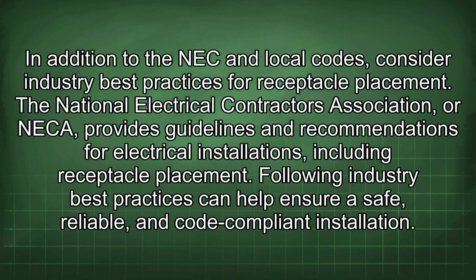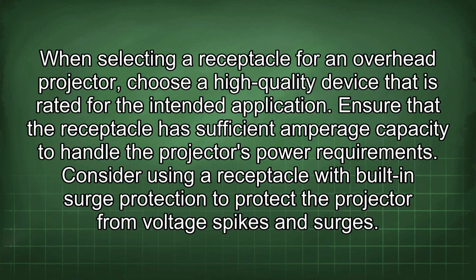In addition to the NEC and local codes, consider industry best practices for receptacle placement. The National Electrical Contractors Association, or NECA, provides guidelines and recommendations for electrical installations, including receptacle placement. Following industry best practices can help ensure a safe, reliable, and code-compliant installation. When selecting a receptacle for an overhead projector, choose a high-quality device that is rated for the intended application. Ensure that the receptacle has sufficient amperage capacity to handle the projector's power requirements. Consider using a receptacle with built-in surge protection to protect the projector from voltage spikes and surges.